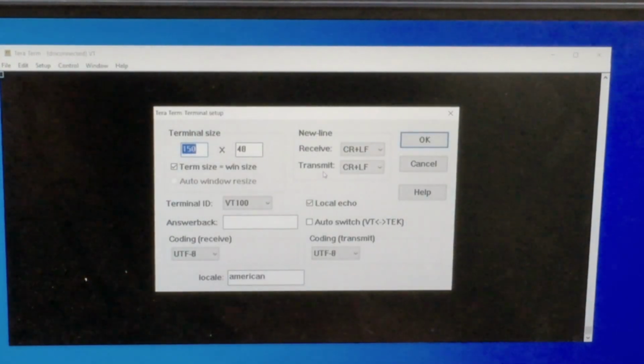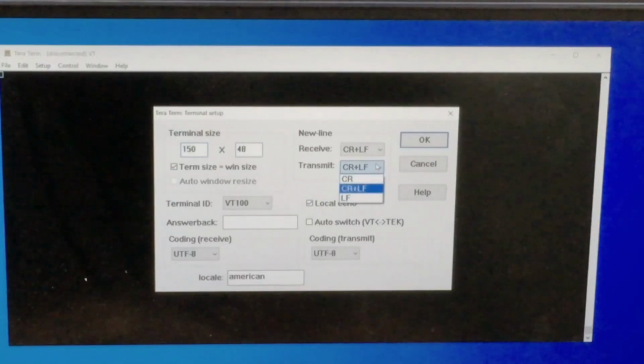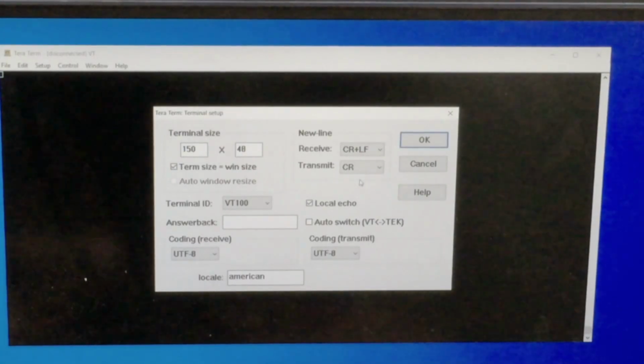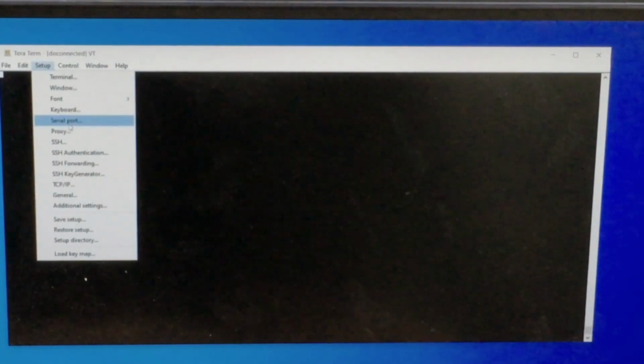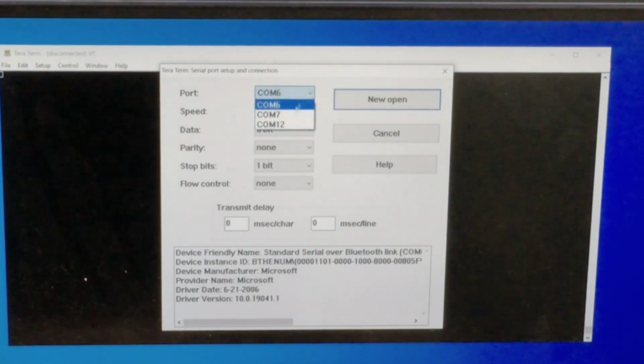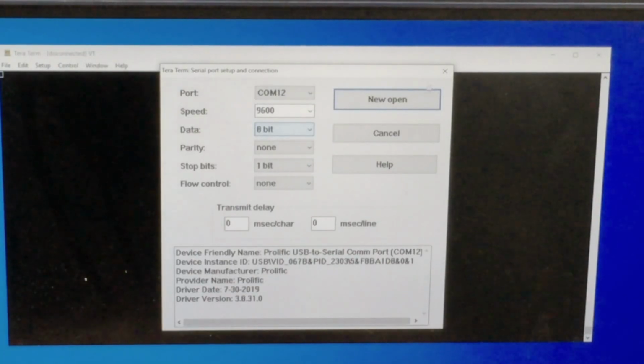To configure the LI-710 sensor, I'm using the TeraTerm software, a terminal emulator. I can connect to the USB to SDI-12 adapter via TeraTerm, and then send commands through it. Before I do that, I have to make sure I set up the terminal correctly. When I send a command, I need to make sure I send it with a carriage return, so I enable the setting to send a carriage return with the commands. Then I want to make sure I make the connection with the right serial port, choosing the serial port the adapter is attached to, at a baud rate of 9600.